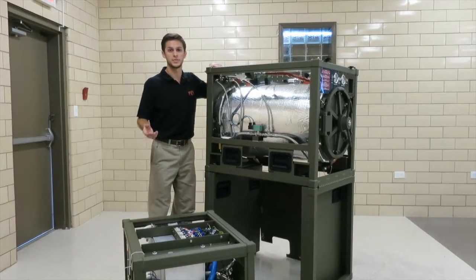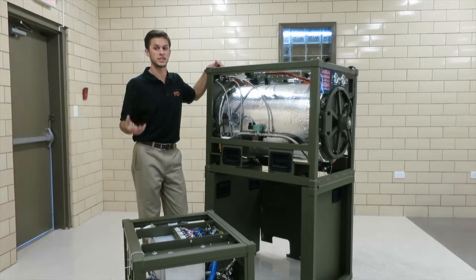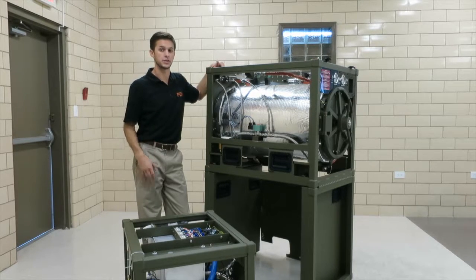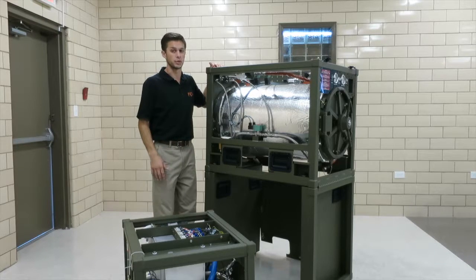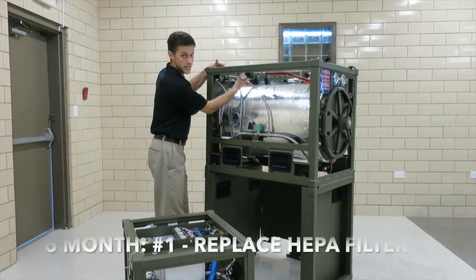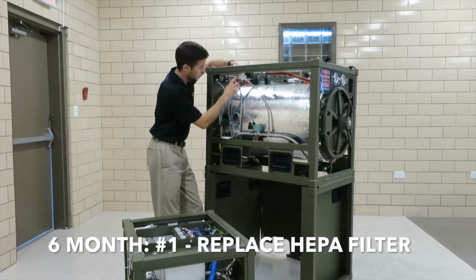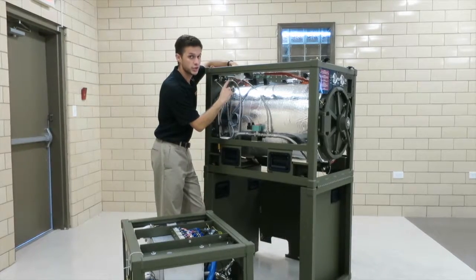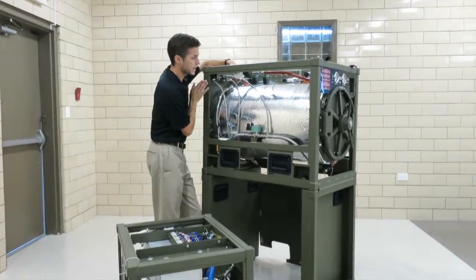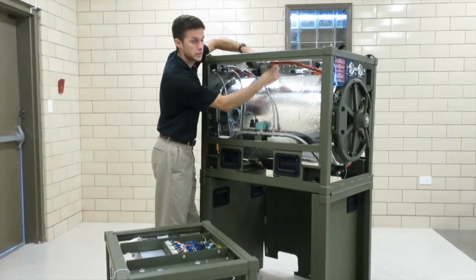So we're going to talk about the preventative maintenance tasks to perform every 6 months. These are listed in the manual. We're going to go in order of the manual. So the first one is to replace the HEPA filter, which is right here. Please note that there's an arrow for direction of flow, and so the arrow should point towards the 2 valves.